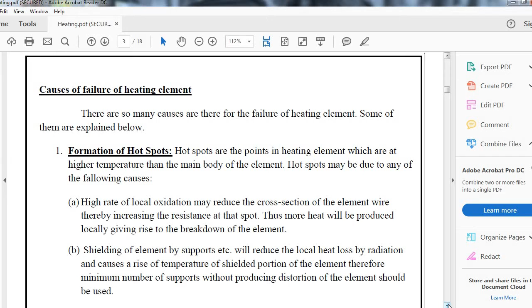High rate of local oxidization may reduce the cross section of the element wire, thereby increasing the resistance at that spot. Thus more heat will be produced, which locally gives rise to the breakdown of the element. Shielding of the element by supports etc. will reduce the local heat loss by radiation and cause a rise in temperature of the shielded portion of the element. Therefore, a minimum number of supports without producing distortion of the element should be used. Due to high element temperature, insufficient support of the element or selection of the wrong material, sagging and warping of the element may result, which may cause uneven spacing of sections, thereby producing a hot spot.